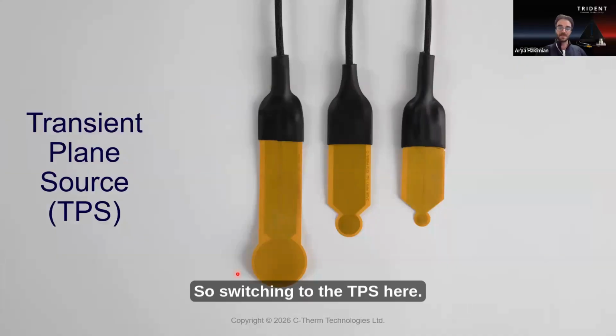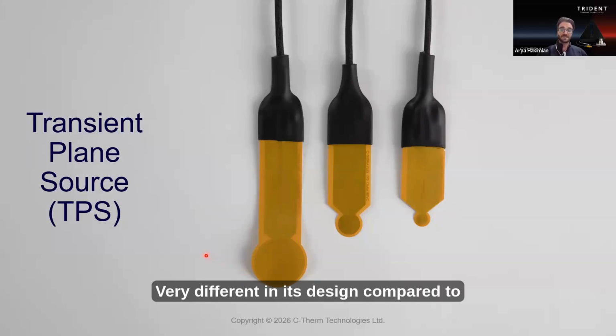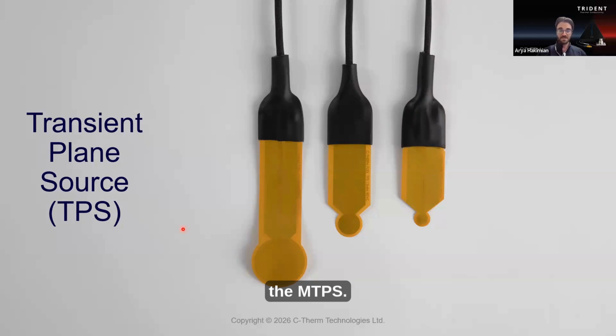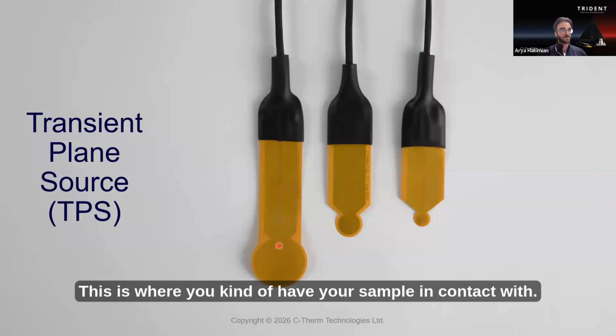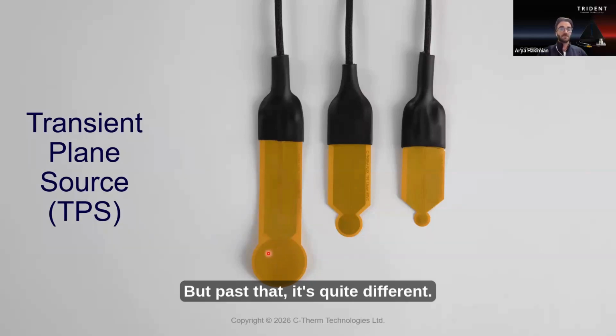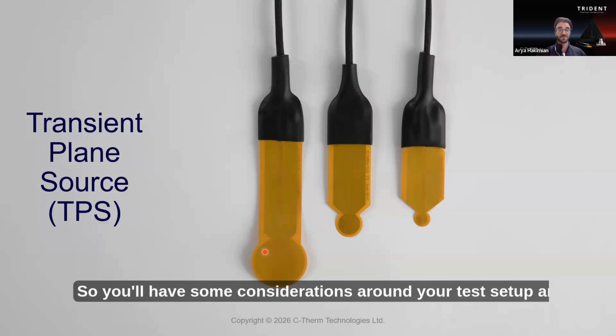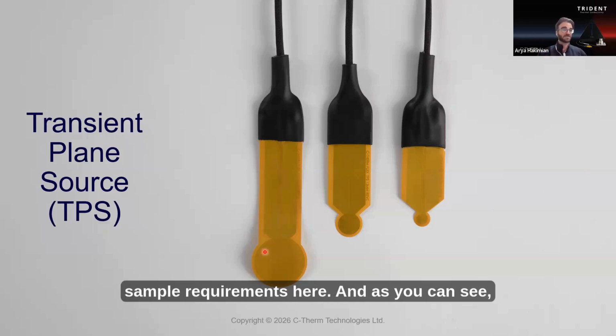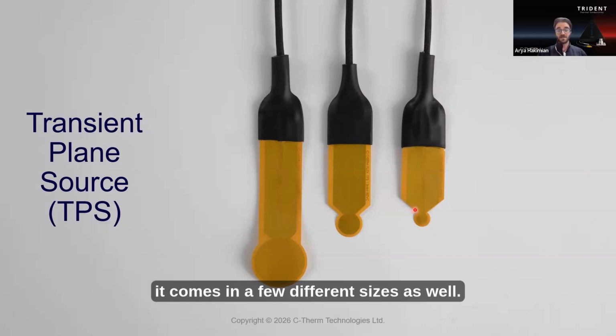So switching to the TPS here. As you can see, TPS is very different in its design compared to the MTPS. It similarly has a circular spiral heating element on the end. This is where you have your sample in contact. But past that, it's quite different. It's very thin, it's flexible, it's actually double-sided, so you'll have some considerations around your test setup and sample requirements here. And as you can see, it comes in a few different sizes as well.